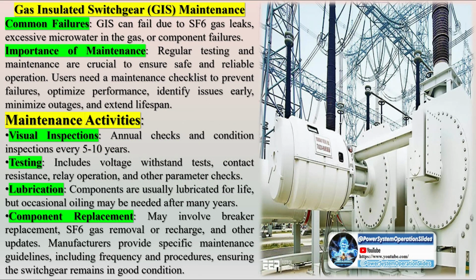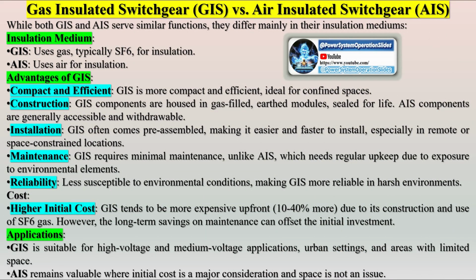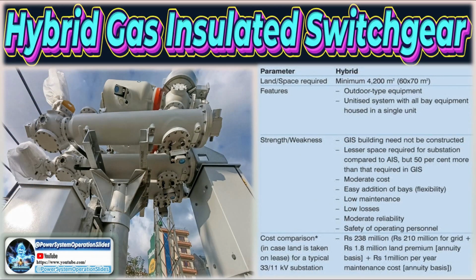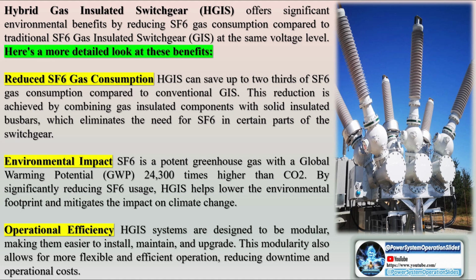The design of gas-insulated switchgear involves using a dielectric gas, typically sulfur hexafluoride, SF6, to insulate various switchgear components within grounded, metal enclosures. The gas is maintained at a moderate pressure of 400 to 600 kilopascals to prevent leakage or condensation at low temperatures. SF6 is a colorless, inert gas that is approximately 5 times denser than air and provides 2 to 3 times better insulation. Its superior arc flash handling capability makes it about 100 times more effective than air. GIS components are pre-assembled and gas-filled at the factory, simplifying the installation process.